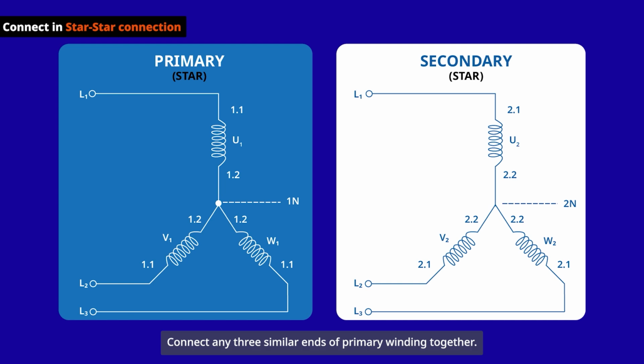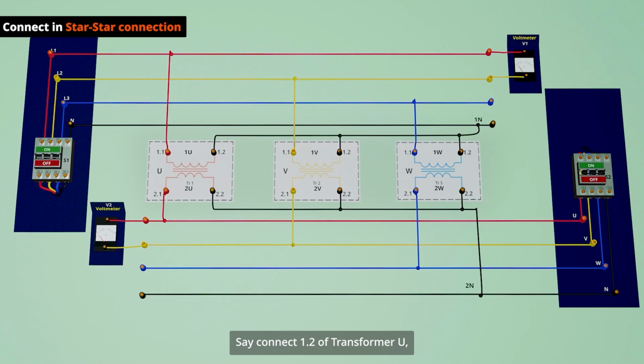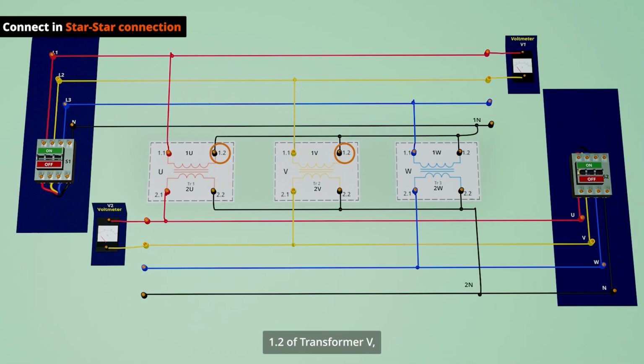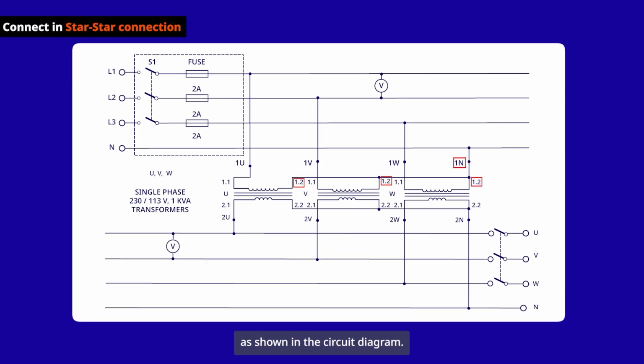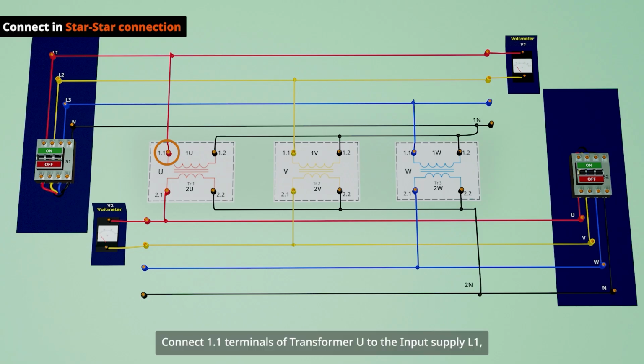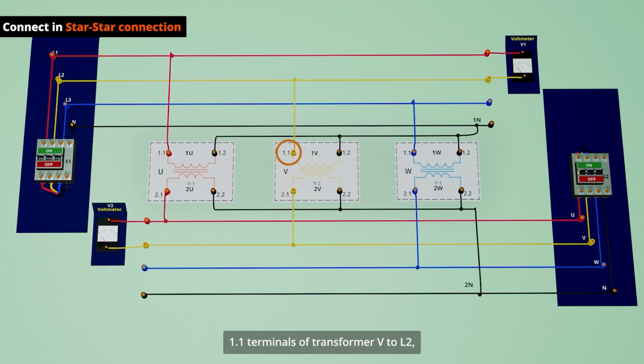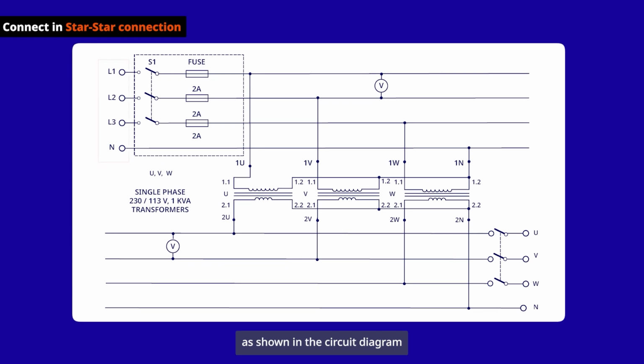To connect in star-star connection, connect any three similar ends of the primary winding together. Say, connect 1.2 of transformer U, 1.2 of transformer V, and 1.2 of transformer W together and mark the junction as 1N, signifying neutral, as shown in the circuit diagram. Connect the 1.1 terminal of transformer U to the input supply L1, the 1.1 terminal of transformer V to L2, and the 1.1 terminal of transformer W to L3, as shown in the circuit diagram.